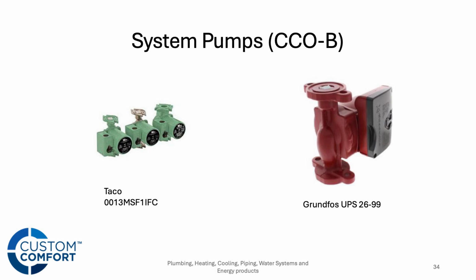The point I'm trying to reiterate here is at the end of the day, the heat only boiler, it's not a 007, it's not a Grundfos 1558. It's that kind of next series up where we can overcome that head pressure and then the flow requirements of these heat exchangers. So think 0013 or a Grundfos 2699 for the heat only system pump.